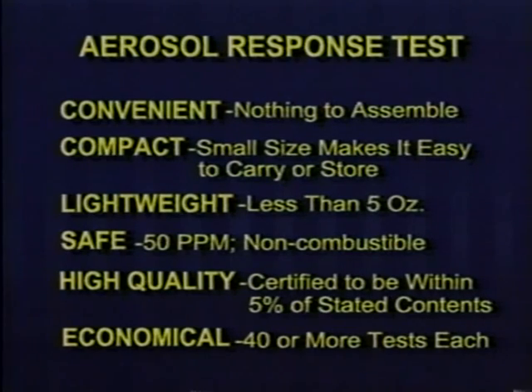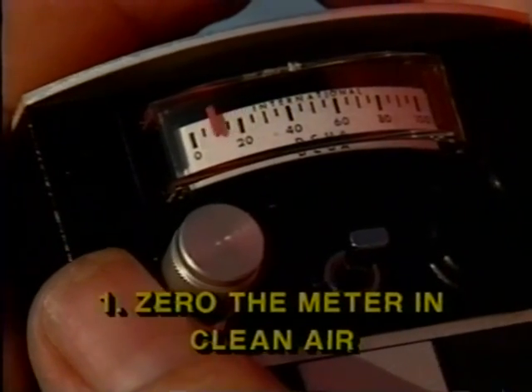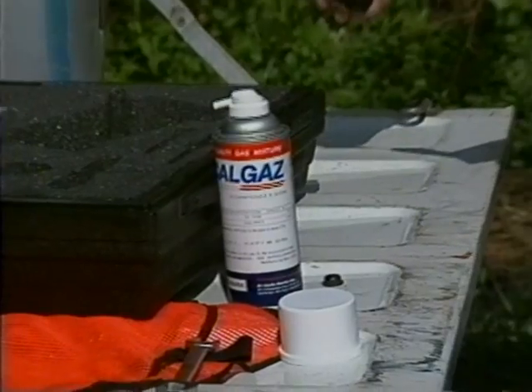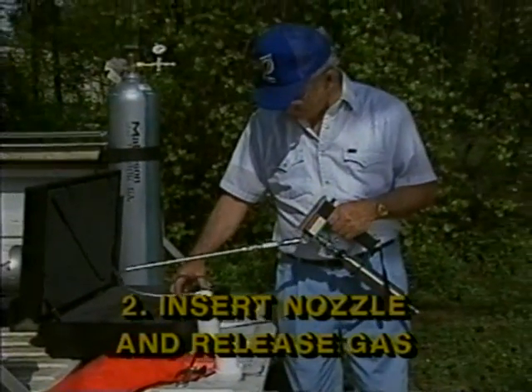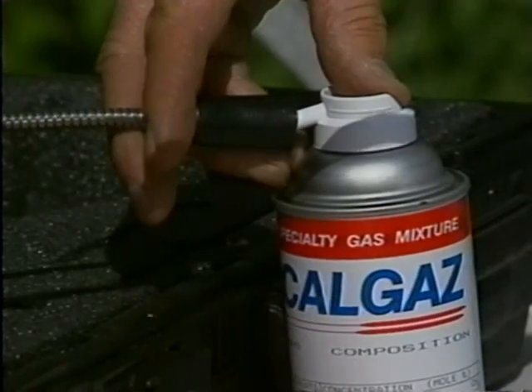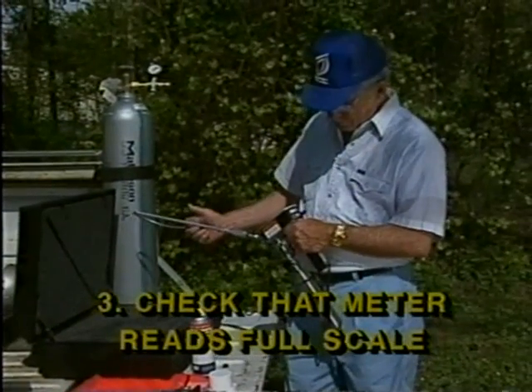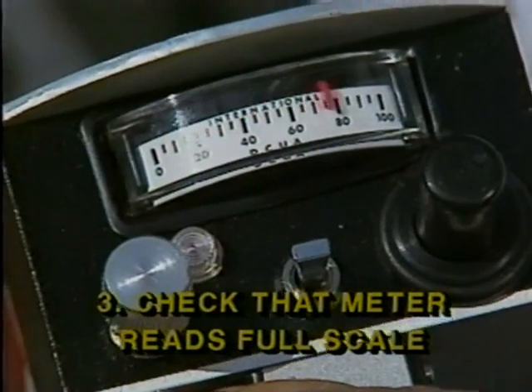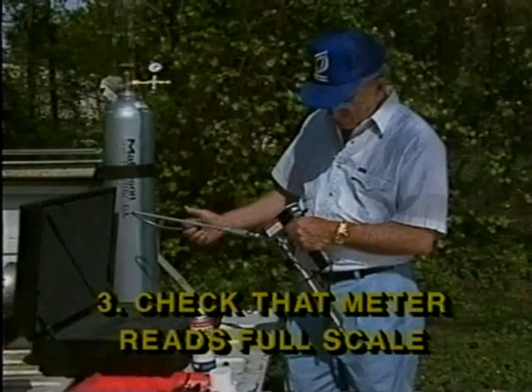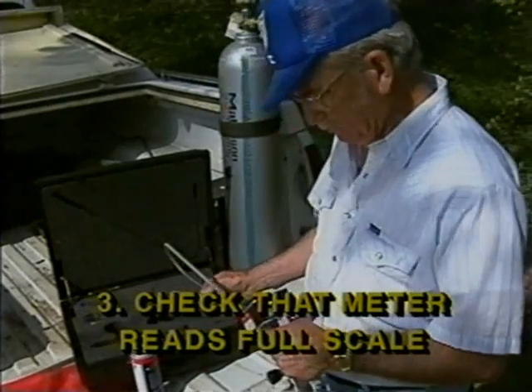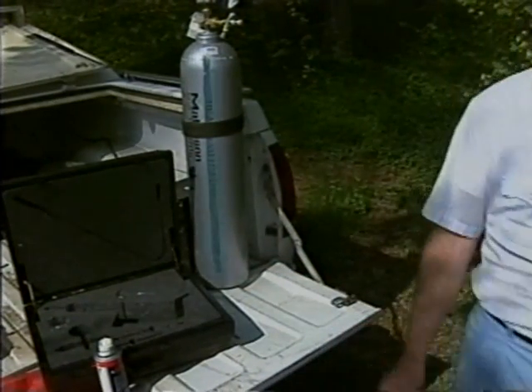As an alternative, you may use the 50 parts per million test kit with its quick, convenient aerosol can. Each can weighs less than 5 ounces and contains enough gas for 40 tests. First, zero the meter in clean air. Next, insert the can nozzle into the intake cone and release a short burst of gas. Now the meter on the flame pack should read at or near full scale. This means the flame pack is functioning properly. The reading you get may vary due to background hydrocarbon levels.